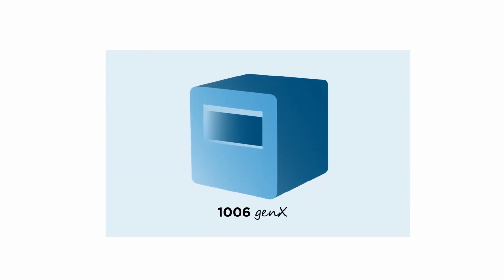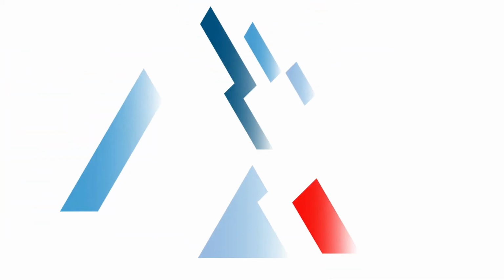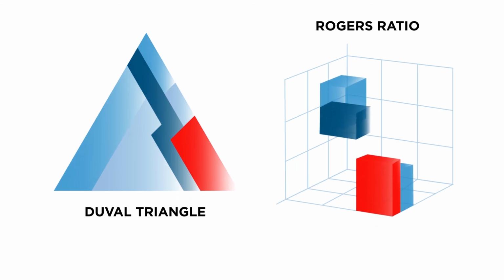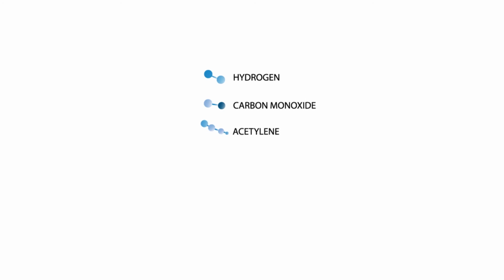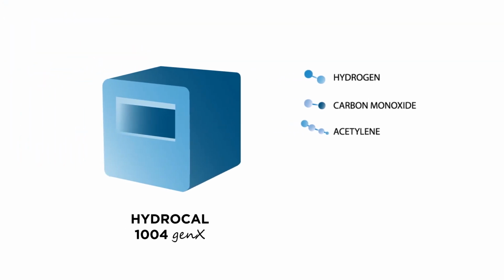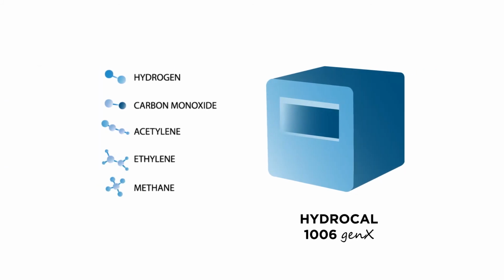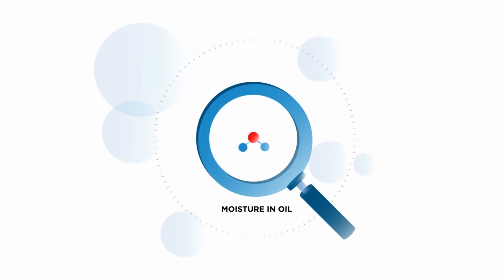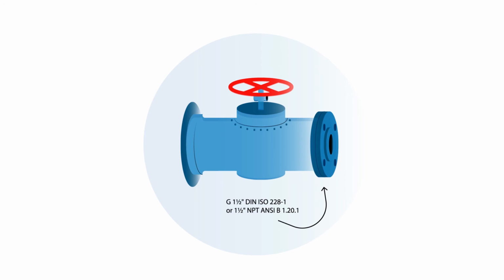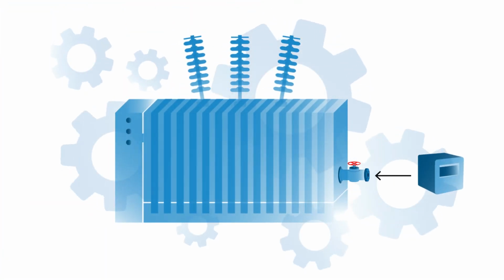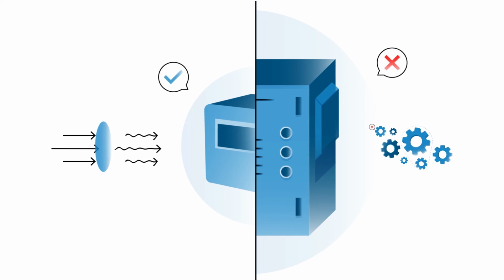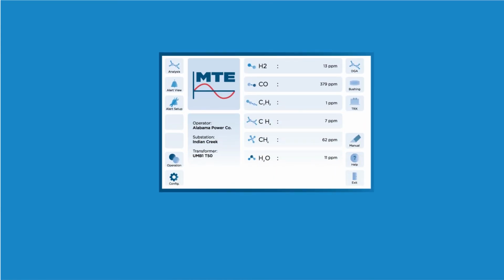The HYDROCAL 1006 genX also provides diagnostic tools such as Duval's triangle or Dornenburg and Rogers ratio. Individual measurement of hydrogen, carbon monoxide and acetylene for the HYDROCAL 1004 genX, and additional ethylene and methane for the HYDROCAL 1006 genX. Moisture in oil measurement. Easy to mount on a transformer valve. Easy to mount on the operating transformer without any operational interruption. Maintenance-free system due to significantly fewer movable parts, only 2 valves and 1 compressor. Advanced software on the HYDROCAL device and via PC with intuitive operation by 7-inch color TFT touchscreen, WLAN and WEBSERVER operation from any smartphone, tablet or notebook PC.